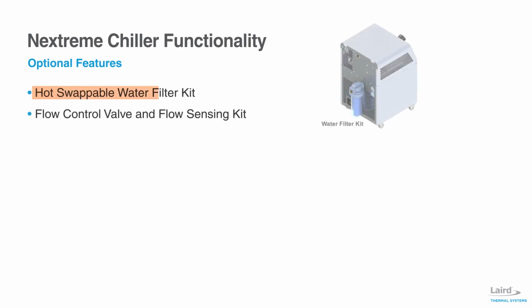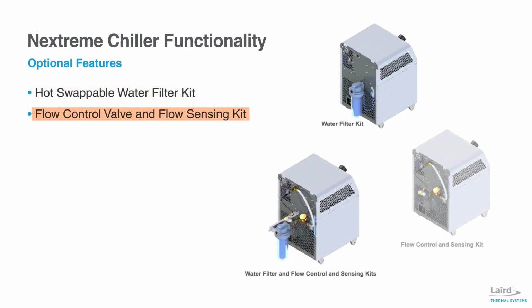The chiller platform offers an optional hot swappable 5-micron water filter for filtering particulates from the coolant circuit. This allows filter maintenance to be scheduled at any time without the need to shut off the unit. The flow control valve and flow sensing kit contains an externally installed valve for controlling the overall fluid flow to the application. Full flow continues through the chiller to maintain high heat transfer rates and temperature stability. The high accuracy, high reliability flow meter measures the coolant flow rate and displays the flow on both the flow meter and on the integrated chiller LCD display. The valve and flow meter kit allow the user to easily set the flow rate to any application.